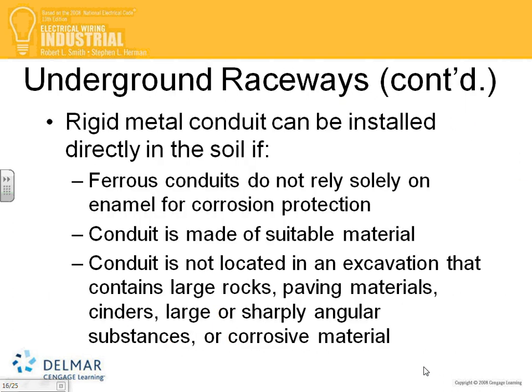Your conduit of choice, guys, for underground is PVC. If you decide to use rigid metal conduit, make sure it's treated for corrosion protection. For example, you can't use aluminum rigid underground. You're going to use steel rigid that's treated for corrosion. Can you use schedule 40 in concrete? Yeah, schedule 40 or 80.